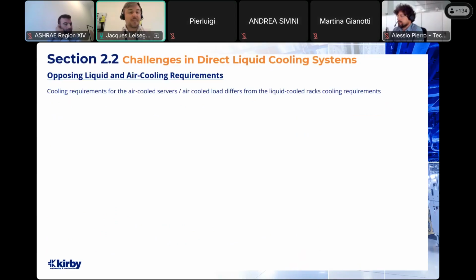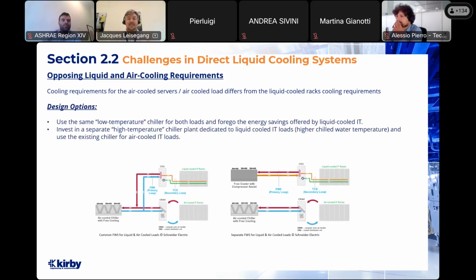So next is the challenge of the opposing liquid and air cooling requirements. The cooling requirements for the air-cooled servers and the air-cooled loads, whether that be electrical rooms or switch rooms, differ from the liquid-cooled racks' cooling requirements. So how is that managed? There are some different options in terms of how the systems can be implemented. Either using the same low temperature chiller for both loads, you then forego any energy savings offered by the liquid cooled IT in terms of temperature optimization. Another option is to invest in separate high temperature chiller plants dedicated to the liquid loads, and then using an existing chiller for the air cooled IT loads.